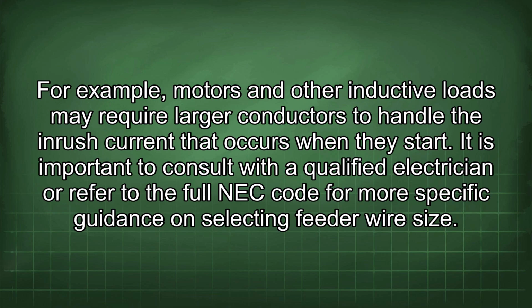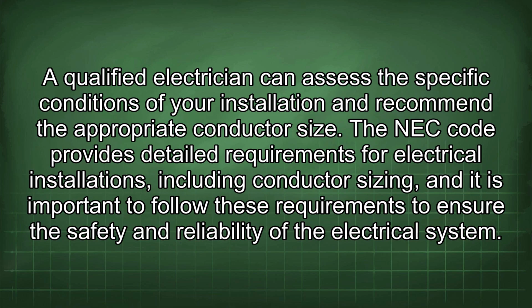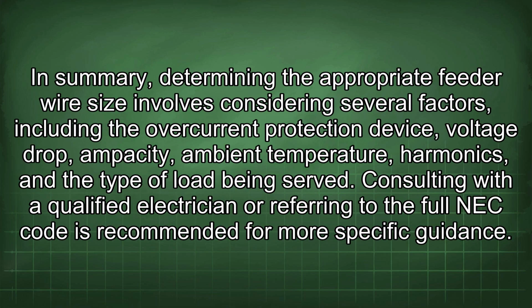It is important to consult with a qualified electrician or refer to the full NEC code for more specific guidance on selecting feeder wire size. A qualified electrician can assess the specific conditions of your installation and recommend the appropriate conductor size. The NEC code provides detailed requirements for electrical installations, including conductor sizing, and it is important to follow these requirements to ensure the safety and reliability of the electrical system. In summary, determining the appropriate feeder wire size involves considering several factors, including the overcurrent protection device, voltage drop, ampacity, ambient temperature, harmonics, and the type of load being served. Consulting with a qualified electrician or referring to the full NEC code is recommended for more specific guidance.